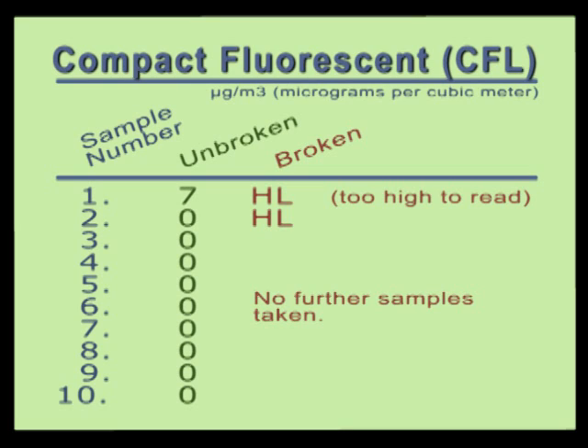At this point, we didn't bother taking any more measurements because when the analyzer gets readings this high, it requires a self-cleaning session and recalibration, which are somewhat time consuming.